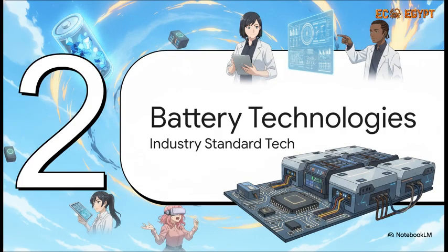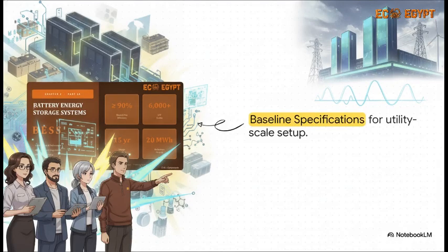Moving on to Section 2, core battery technologies, the industry standard tech. When we're dealing with a utility scale setup, the baseline specs are intense. We're talking designing for a round-trip efficiency of 90% or higher, and we expect over 6,000 cycles out of our lithium iron phosphate, or LFP cells. Honestly, that means the battery is going to outlast a lot of the inverters hooked up to it. Plus, we're demanding a 15-year design lifetime, all applied to a massive 20 megawatt-hour reference project. This isn't residential guesswork, guys. These are the strict technical parameters you need for utility-scale viability.